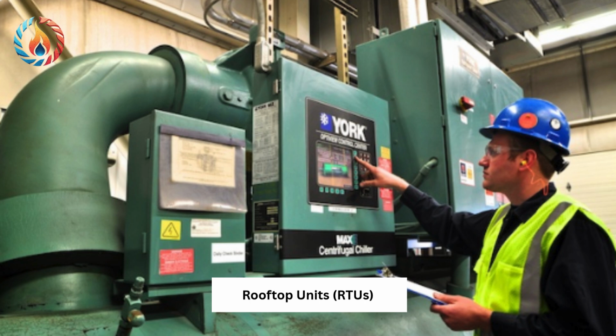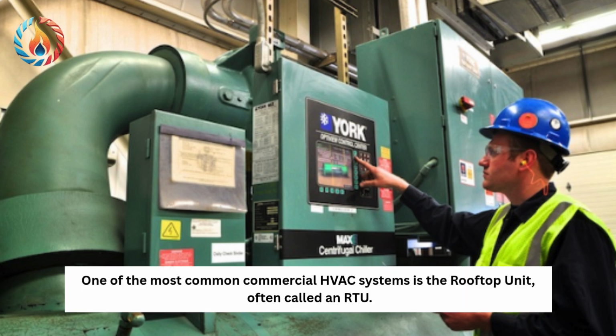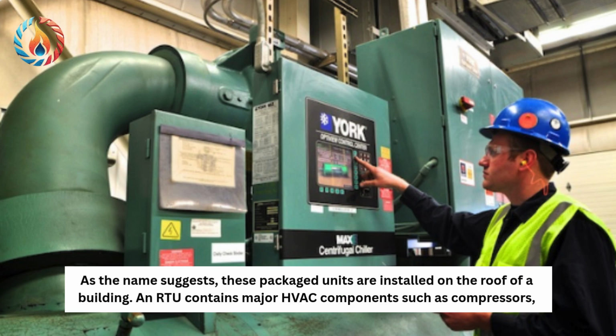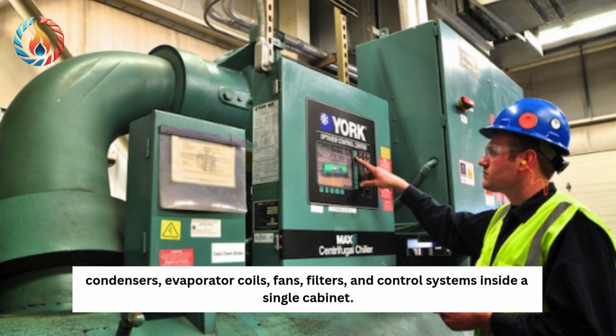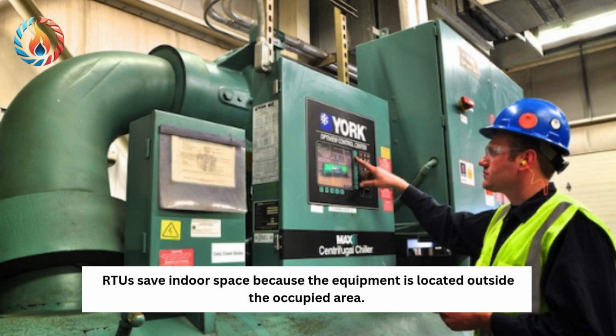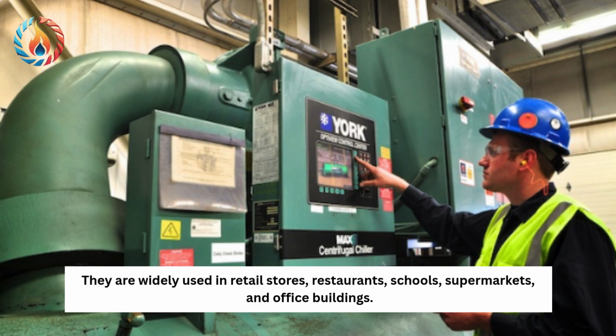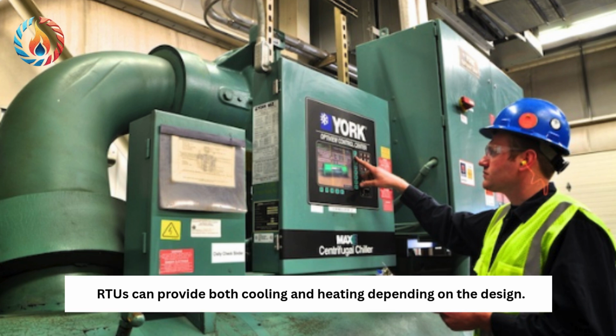Types of commercial HVAC systems. Rooftop units, RTUs. One of the most common commercial HVAC systems is the rooftop unit, often called an RTU. As the name suggests, these packaged units are installed on the roof of a building. An RTU contains major HVAC components such as compressors, condensers, evaporator coils, fans, filters, and control systems inside a single cabinet. RTUs save indoor space because the equipment is located outside the occupied area. They are widely used in retail stores, restaurants, schools, supermarkets, and office buildings. RTUs can provide both cooling and heating depending on the design.